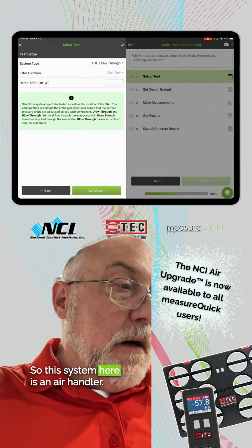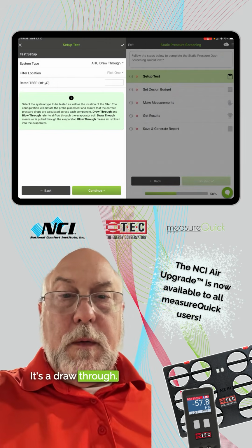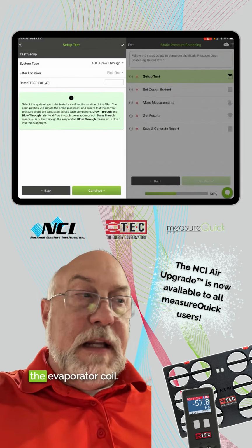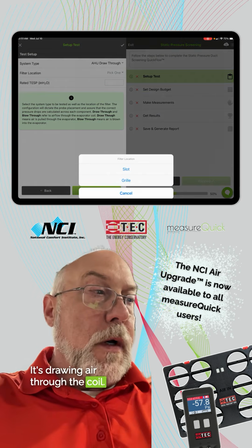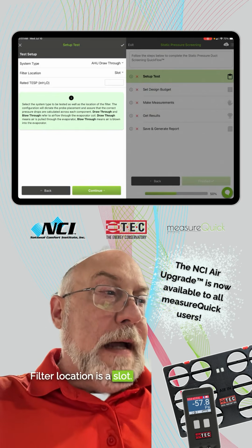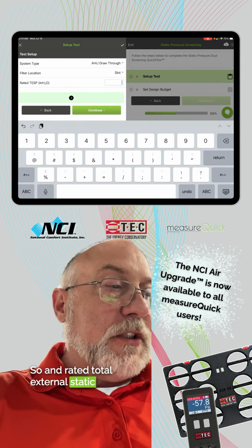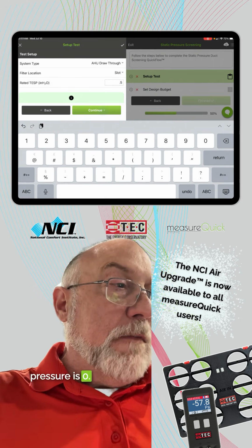So this system here is an air handler. It's a draw through. Draw through meaning the blower's after the evaporator coil. It's drawing air through the coil. Filter location is a slot. So, and rated total external static pressure is 0.5 inches.